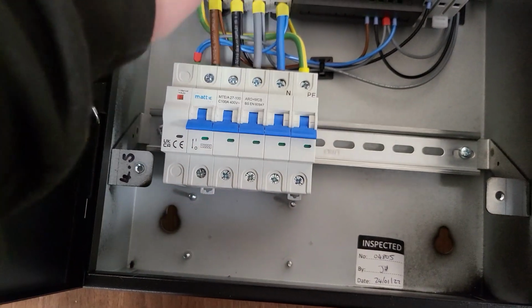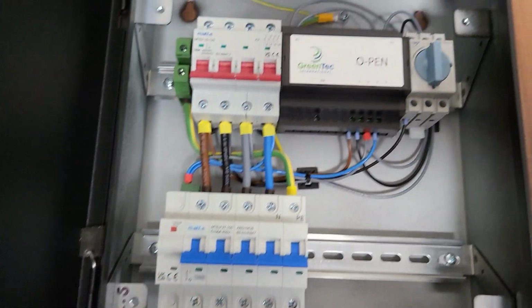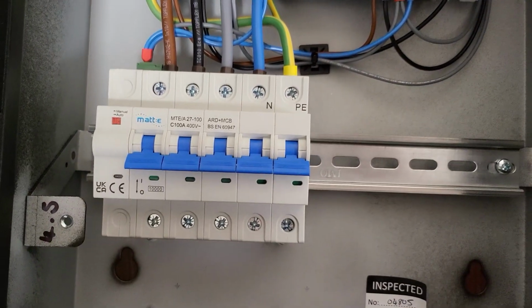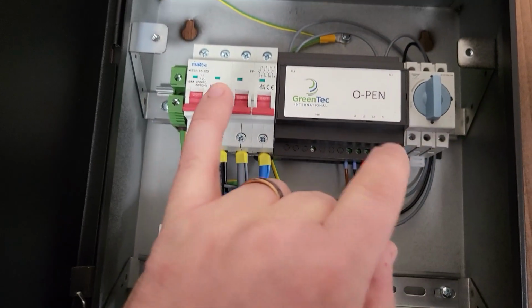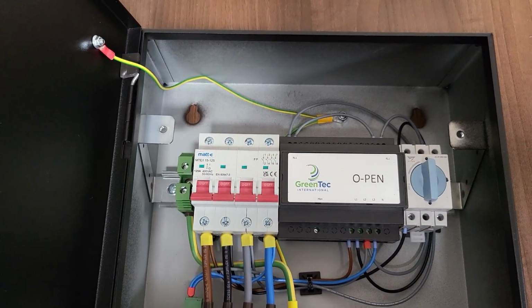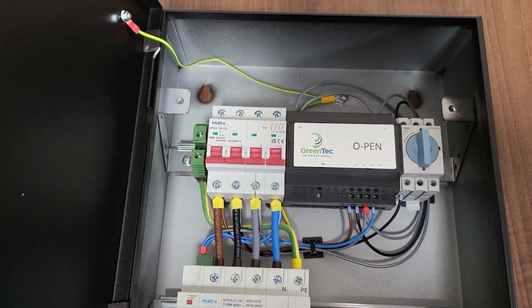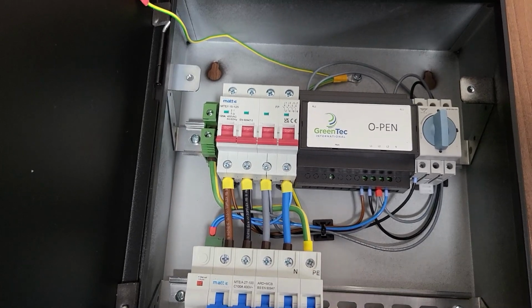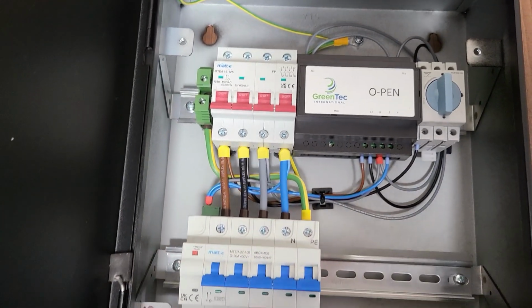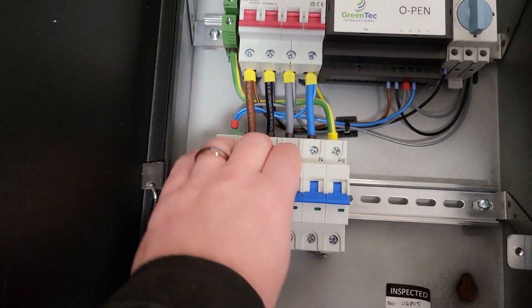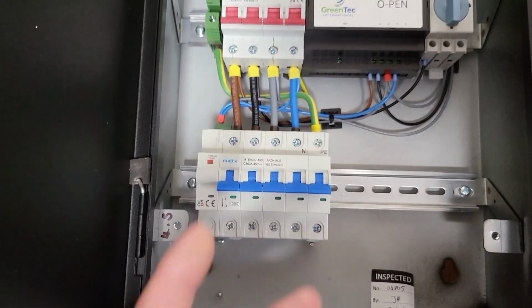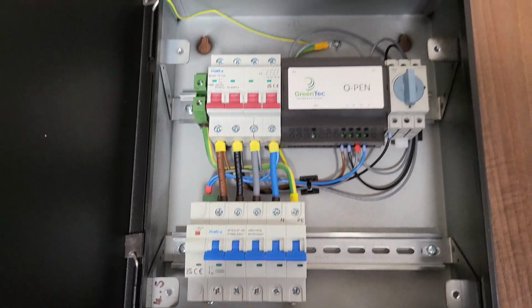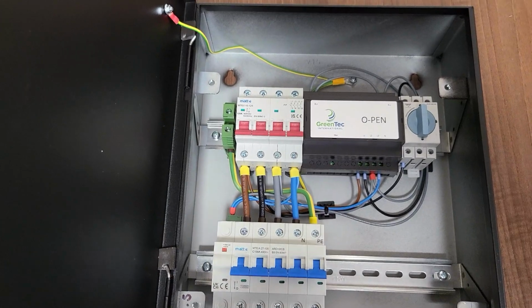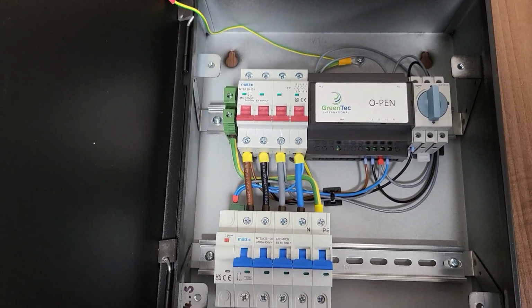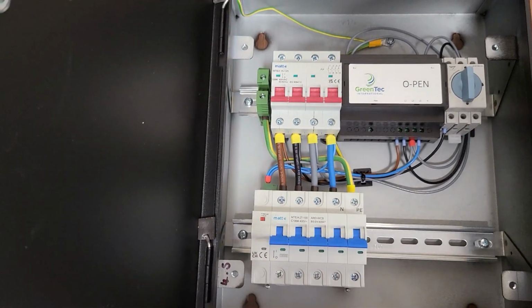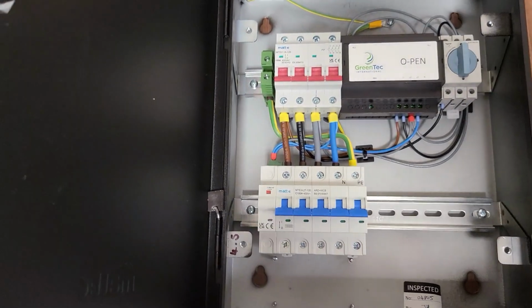But you see here, if I try and hold that in the on position, it doesn't want to know, because obviously there's no voltage in here, so none of this will hold and allow any kind of connection to the outgoing circuits unless you have got power connection with the neutral and the earth, and that there is no anomalies in any of that. As soon as it sees a loss of a phase or a rising voltage on the earthing conductor, is essentially the basic principle, it will not allow this to stay in a closed position. It opens it, disconnects the load of all conductors, so that charge point essentially just becomes a piece of plastic and metal on the wall that can't present any danger to a user beyond the electric vehicle that might be connected to it. So that's how these things work.